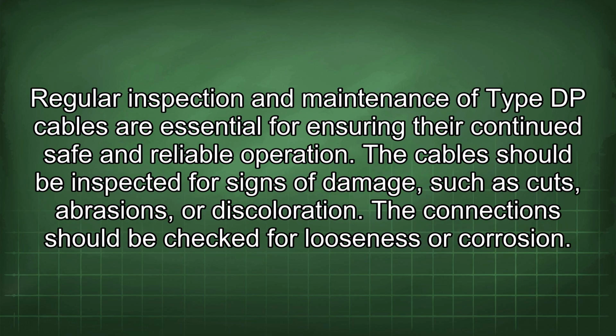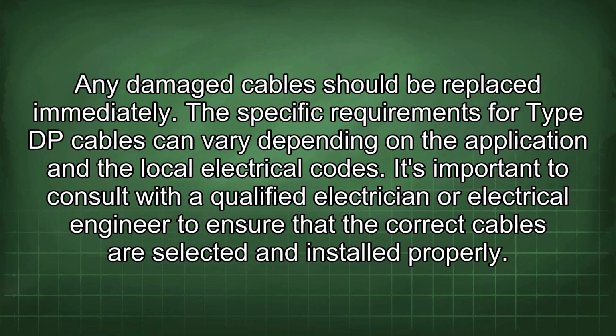Regular inspection and maintenance of Type DP cables are essential for ensuring their continued safe and reliable operation. The cables should be inspected for signs of damage, such as cuts, abrasions, or discoloration. The connections should be checked for looseness or corrosion. Any damaged cable should be replaced immediately.